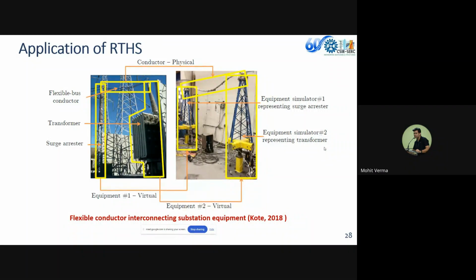Here you can see we have a flexible bus conductor connected to a surge arrestor and transformer. Instead of testing the surge arrestor and transformer directly, we use a tower assembly called the equipment simulator. Each equipment simulator tries to simulate the rocking behavior of the surge arrestor and transformer, and then we have the interconnected cable.